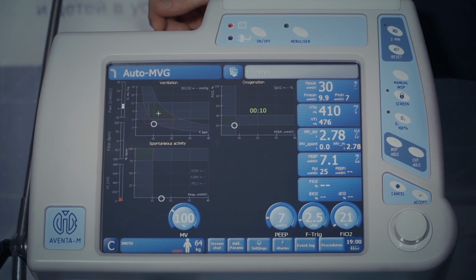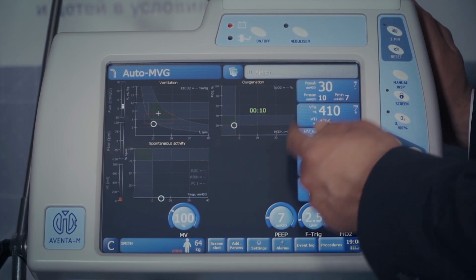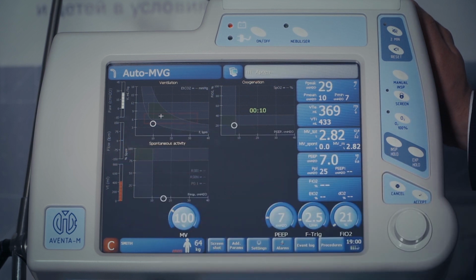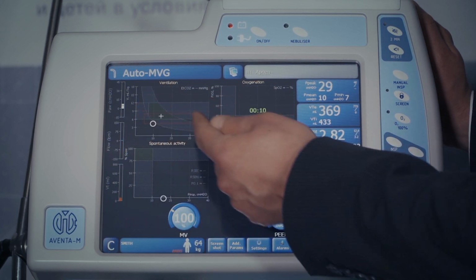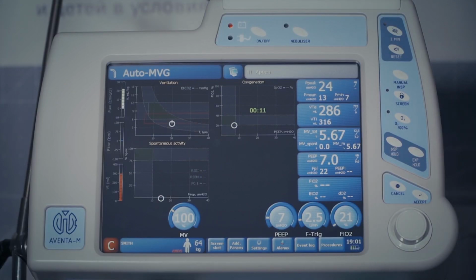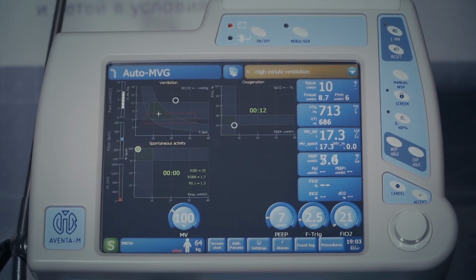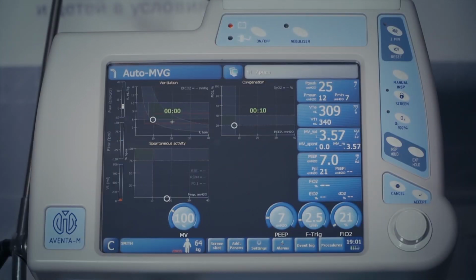This run screen combines 3 graphic windows that indicate ventilation, oxygenation statuses of a patient and his or her spontaneous activity. The current ventilation status is displayed in the ventilation window in the form of a ring. The boundaries for safe ventilation of a patient, considering respiratory mechanics and mode settings, are indicated with a red color. Ventilation goal is indicated with a cross. This ventilation goal represents an ideal ratio of respiratory volume and rate when the preset minute ventilation volume is achieved with minimal effort. With every breath, the ventilator gradually adjusts the respiratory volume, inspiration pressure, and respiratory rate in order to achieve the optimum ventilation.